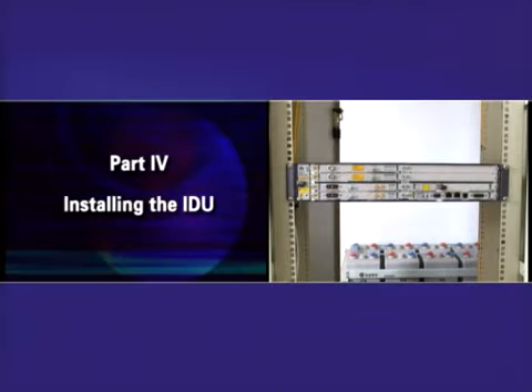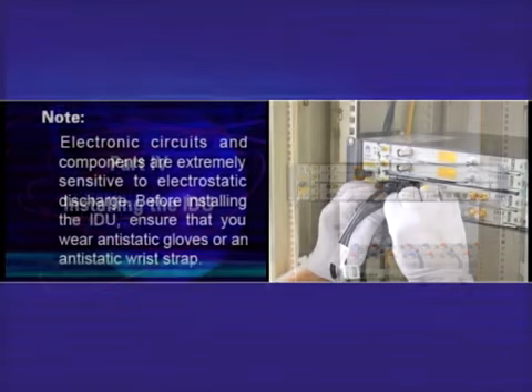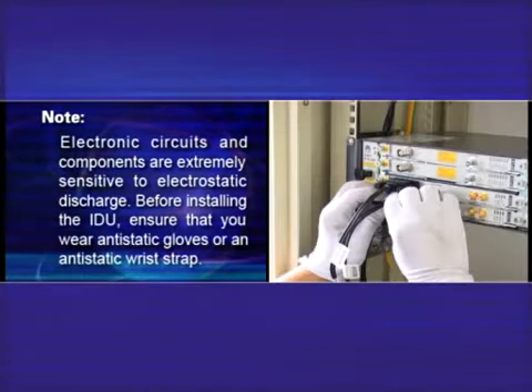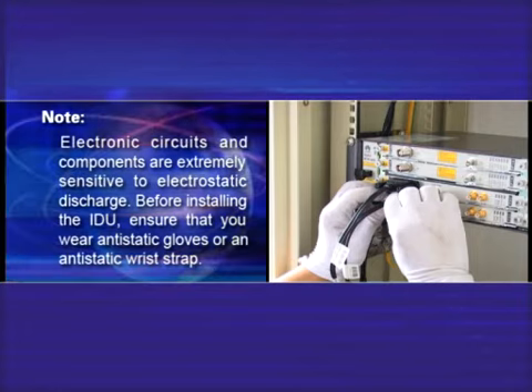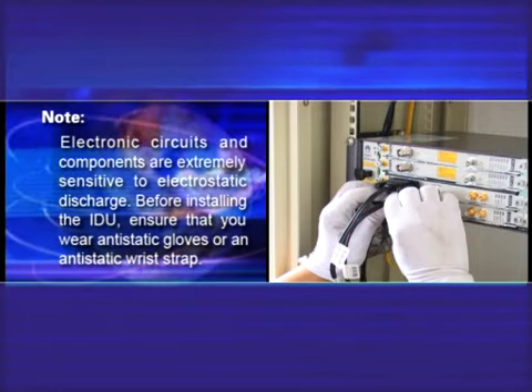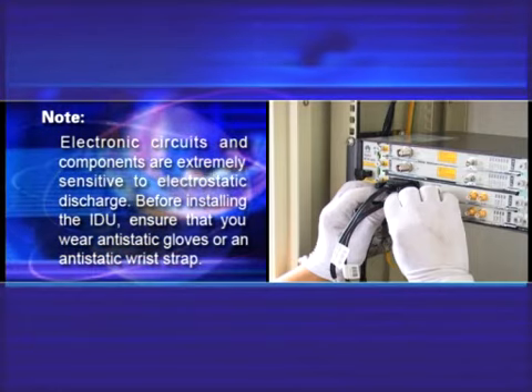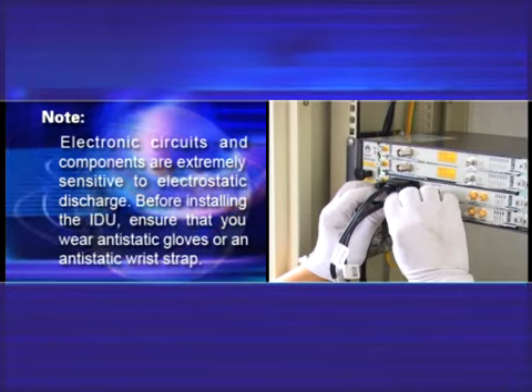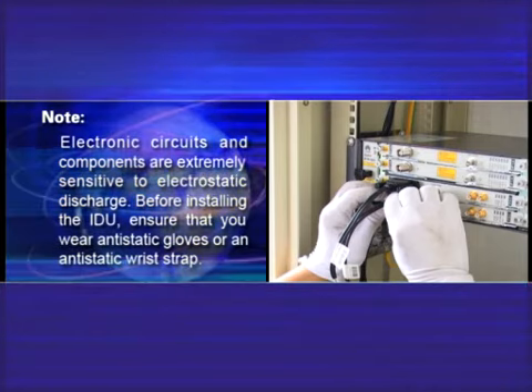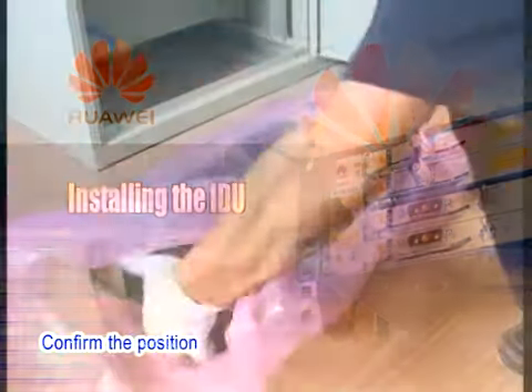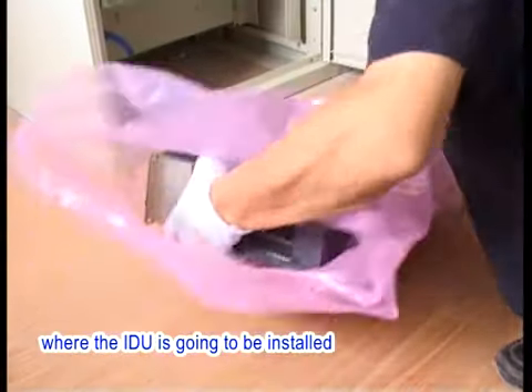Part 4. Installing the IDU. Note: electronic circuits and components are extremely sensitive to electrostatic discharge. Before installing the IDU, ensure that you wear anti-static gloves or an anti-static wrist strap. 1. Installing the IDU. Confirm the position where the IDU is going to be installed.